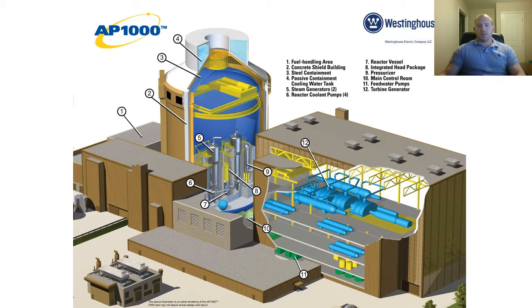The steel containment is 1 and 3/4 inches thick, high integrity steel, and then surrounded by the concrete shield structure, and the 2 of them combined can withstand an aircraft or a missile strike. The spent fuel pool features a 1 meter thick, heavily reinforced concrete, and it's lined with steel. It can also withstand a missile or aircraft strike. The spent fuel will remain covered with water sources located in the spent fuel building for at least 3 days. Following that 3 days, water is provided by the ancillary storage tank. It's a robust design, and it can also withstand all of the natural disasters thrown at it. The control room has a 72-hour air pressurization system and is heavily shielded to keep operators' doses to a minimum.